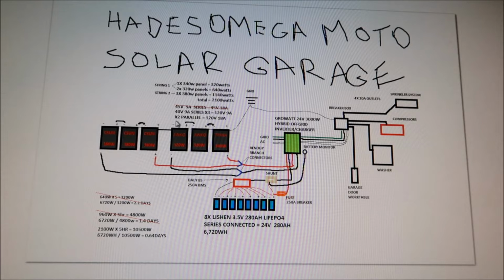So I just put times 2 parallel, and it says 120 volts right here. It's still 120 volts because we're in parallel, but it makes double the current now - 18 amps. We're still good on the wiring, I think it's good for up to 50 amps. So we could probably add 2 more strings before we have to do another wiring run.